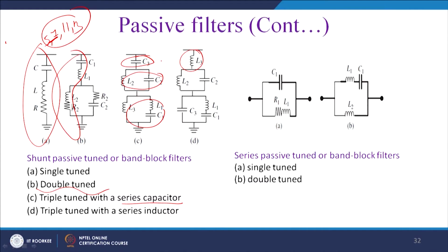So, a triple tuned capacitor will have the advantage of cost, but it requires a control mechanism, otherwise capacitors may actually charge or discharge and they give you a phenomenon of resonance. Whereas when you have these combinations of inductor tuned, it is quite safe, but the system solution will be bulky.